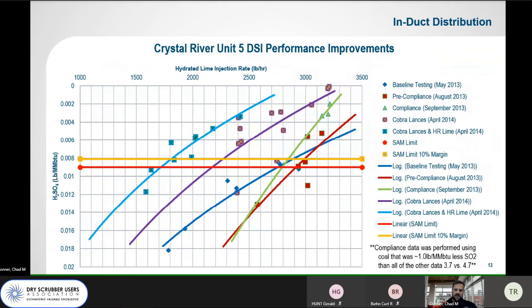Because Crystal River had an SO3 limit, there's a significant amount of SO3 data that was performed consistently at the same locations in the stack. So we had a large mass of SO3 data and felt very comfortable with the testing results. The far left family of curves with the green, red, and dark blue are all of our baseline data with the original configuration. The purple line was data taken after the Cobra lances were installed. And the light blue was the combination of Cobra lances and high reactive lime.